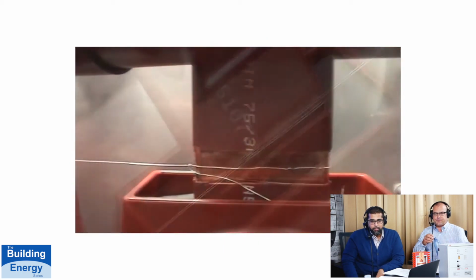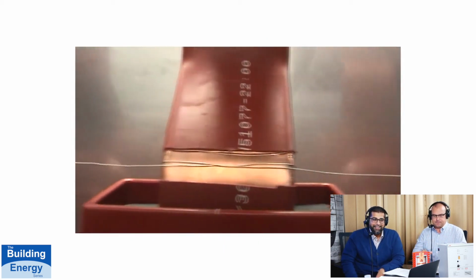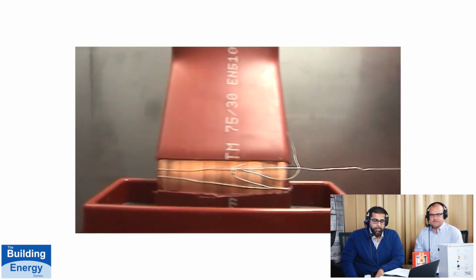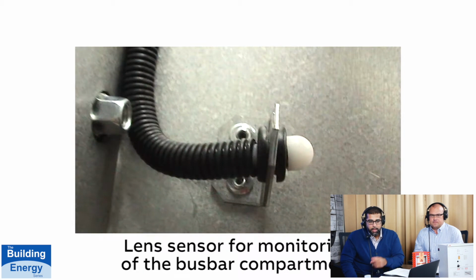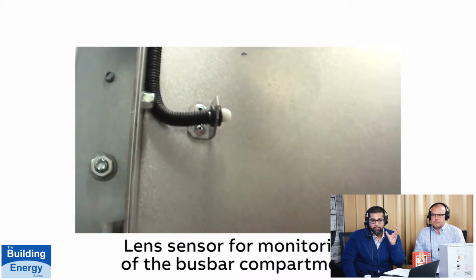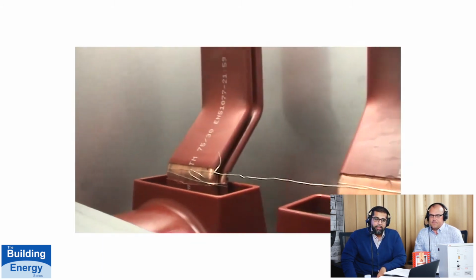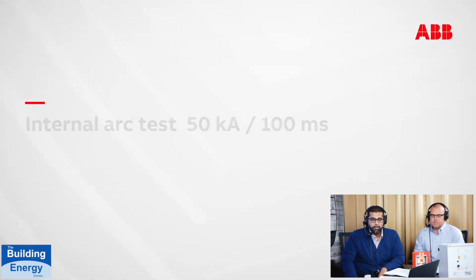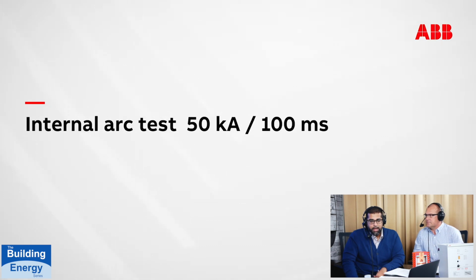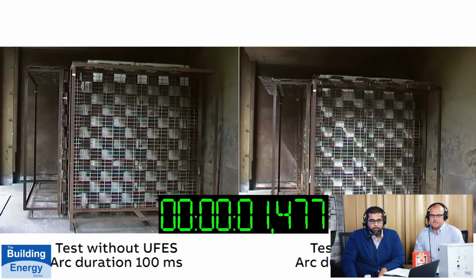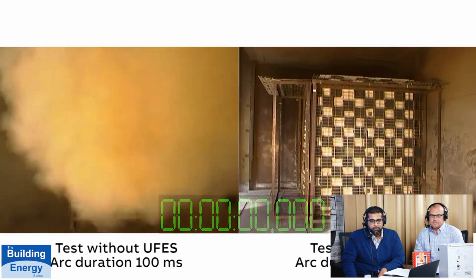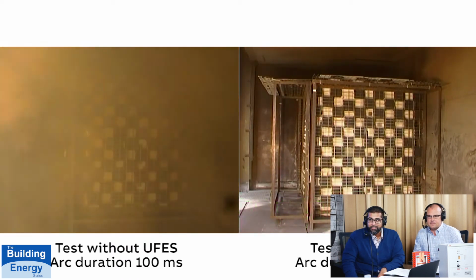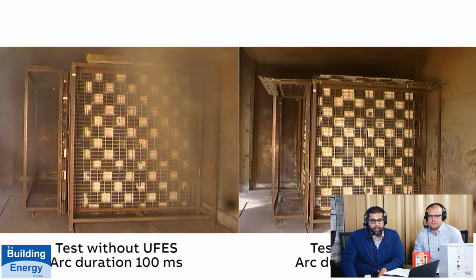This would not be the case in a normal sense. You don't want to have anything there. But because this is an arc flash test, an internal arc test, that's how they do it. Now, these are the lens sensors. This is what will detect the presence of overwhelming light in the compartment. And obviously the current, it's connected to a CT input in the back of the unit as well. Now you'll see the internal arc test at 50 kiloamps for 100 milliseconds. On two sides, on your left-hand side, that's switchgear without the UFES, and on the right-hand side, switchgear with the UFES. The next few seconds will show the amount of damage that takes place.